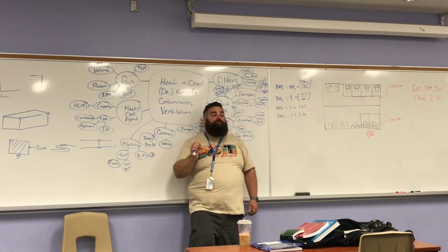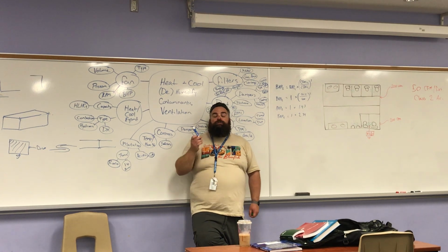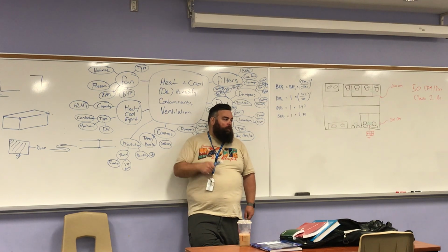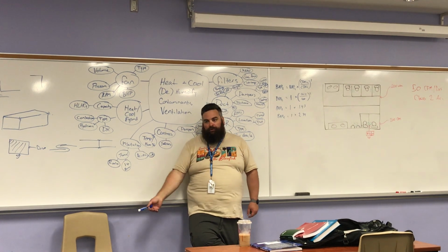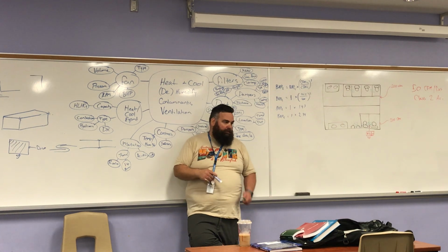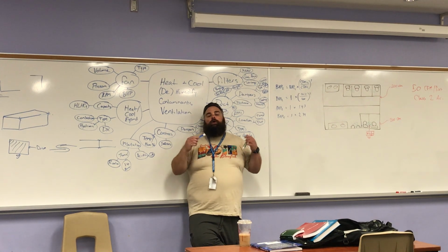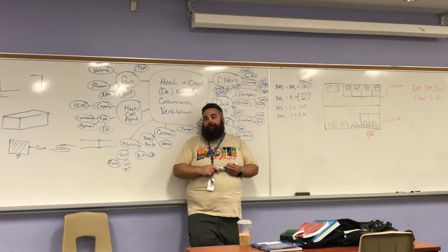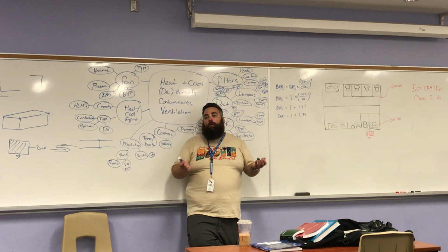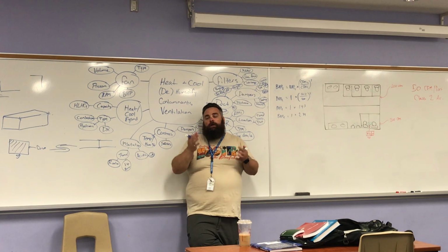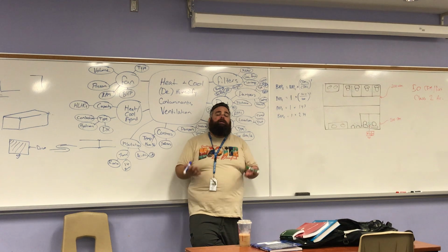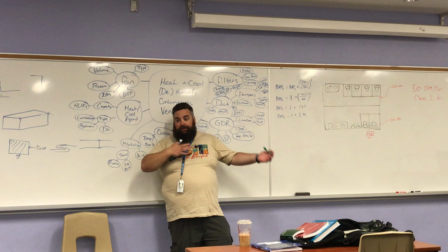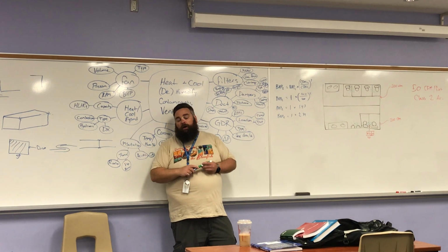The other thing is, it's very, very common to have the landlord dictate what roofer you're allowed to use, because they have a warranty on the roof, so you don't get to bring in your own trade. You gotta use their guy that's gonna honor it, okay? So that's part of the problem with that. Also, over time, that's a point of entry for water, for bugs and whatnot. That's another hole in the roof that's gonna leak hot air, okay? So those are the downsides. Typically, they're offset by the savings in running it across, putting in the wall penetration in the wall.